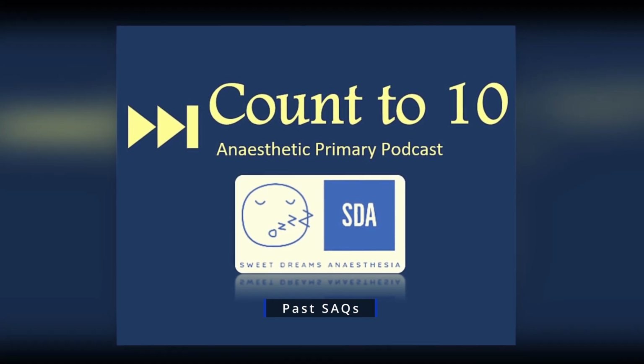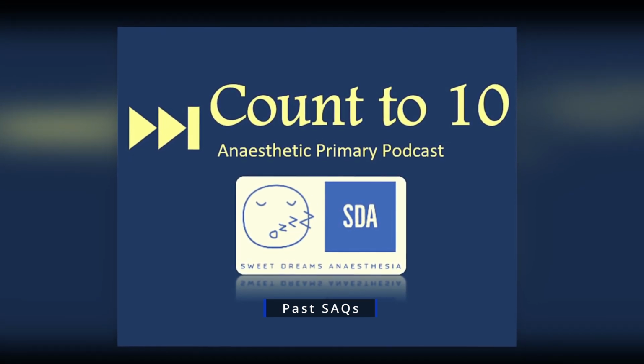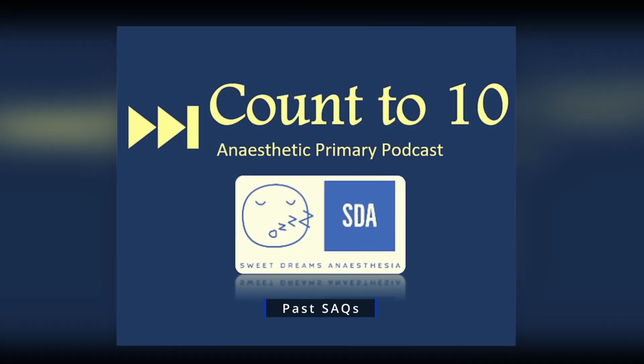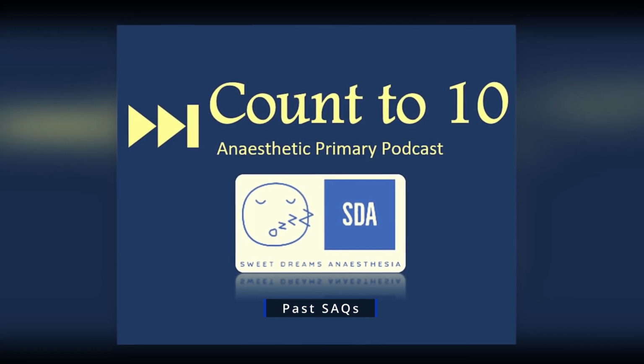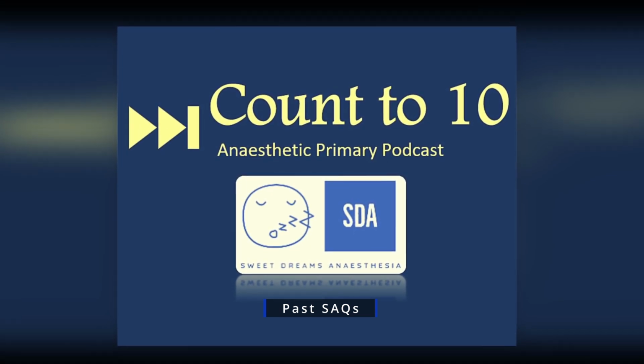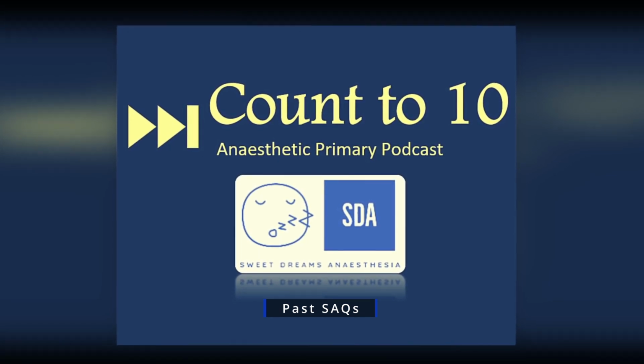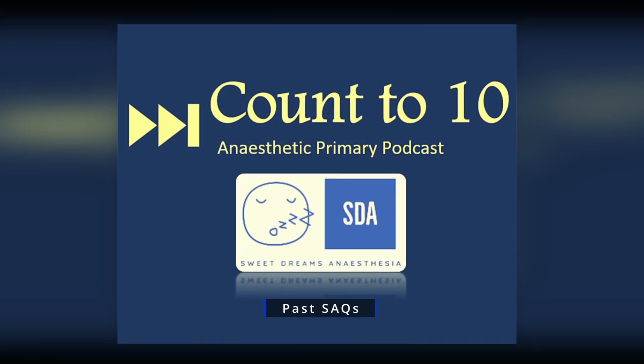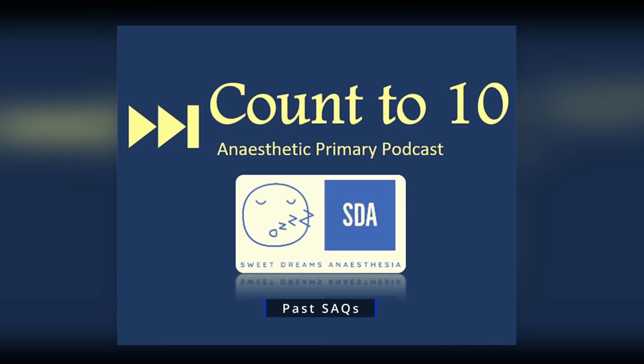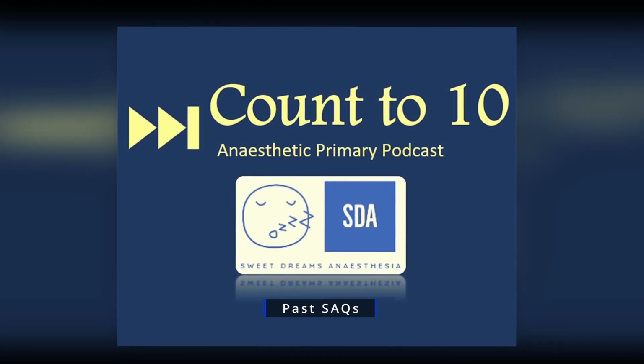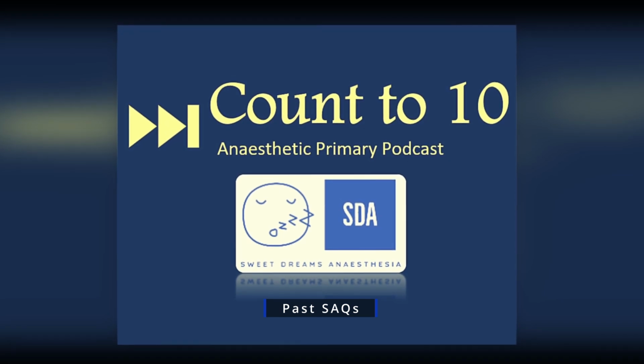So in terms of the device and its components, well, you have the cuff, with the inflatable bladder. You have the port for air insufflation. You have the connection to the transducer and the transducer being in the module itself. And then you have a processor and a display which shows you the systolic, the diastolic, and the mean arterial blood pressure. We talked about proper selection of the cuff already, and this goes back to the 40-80 rule, with the bladder length being ideally 80% of the patient's arm circumference measured in the mid portion of their upper arm, and the bladder width being 40% of the arm circumference.